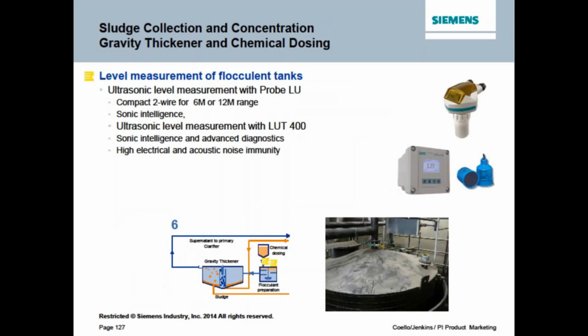If we compare an accuracy spec between an ultrasonic and a radar, our best ultrasonic has a 1 millimeter accuracy spec, which is best in class for any ultrasonic and can beat any radar that we offer. And again, with some of these larger open channel applications, a 1/4 inch or 1/2 inch difference in head height or in level might equal a 500,000 or 1 million gallons per day of flow. So we want to be as accurate as possible. And then the last thing is we have shorter ranges for our ultrasonics than we do for our radar. And because of that, you have more resolution in your range that you're measuring. And most of these open channel applications are only measuring a few feet of range. So we want as much resolution as we can possibly get.